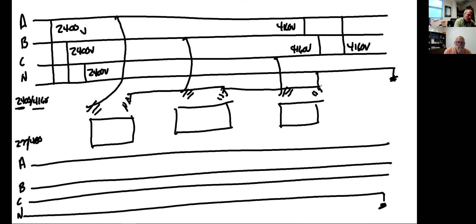Okay, I'm using 3 transformers, same as before. I like it this way. A, B, C. I'm going to work on my grounded neutral bushing. 1, 2, connect here, come over to here. I remembered from before, hey, closed delta is the only bank that floats, so I need to connect this one.